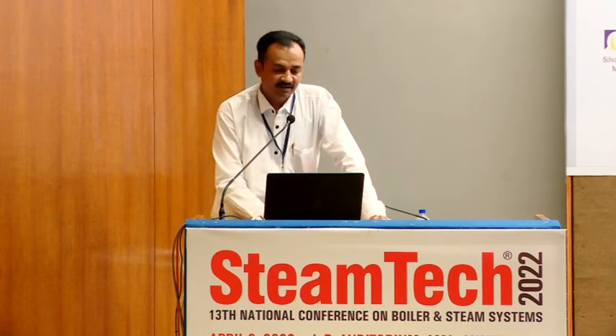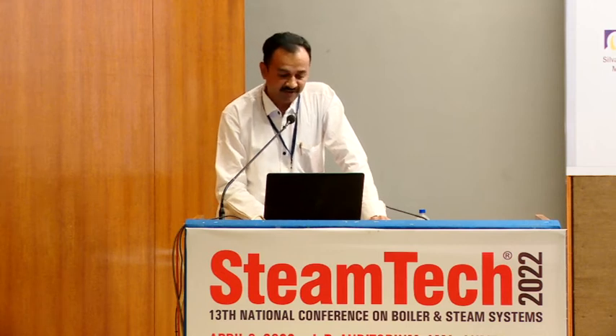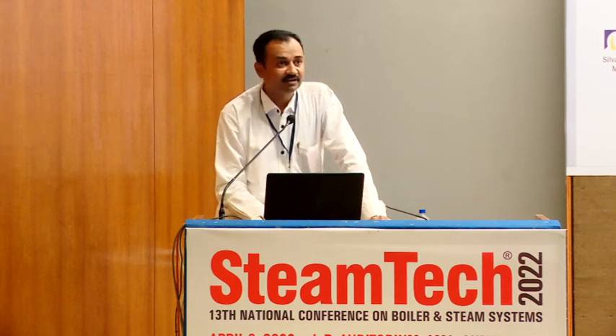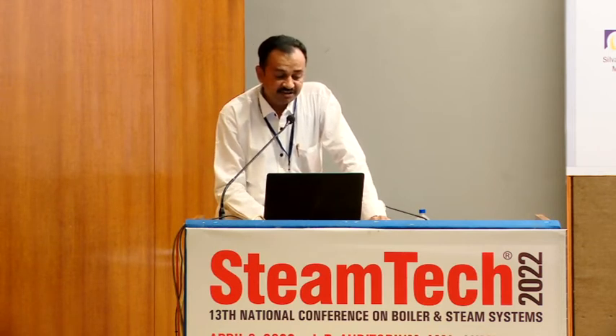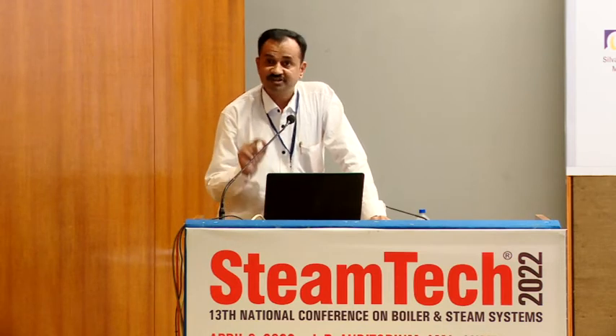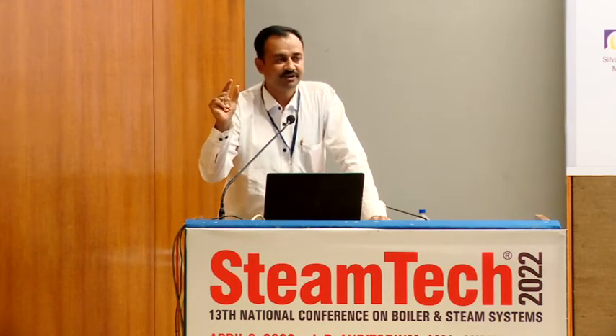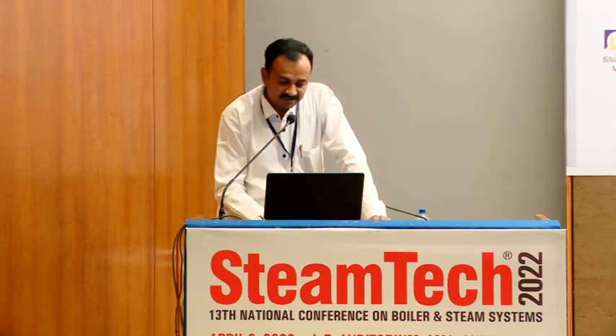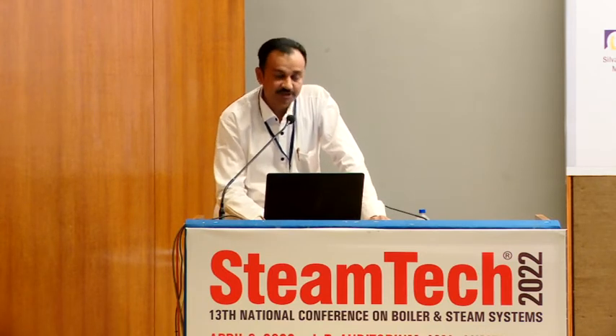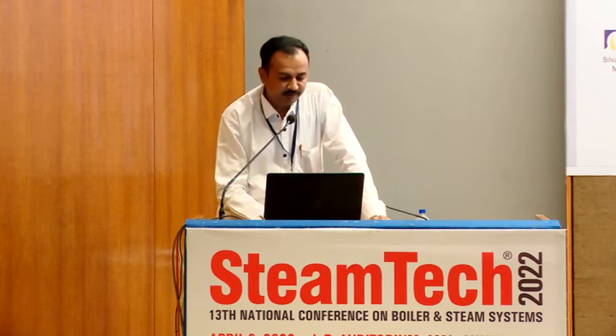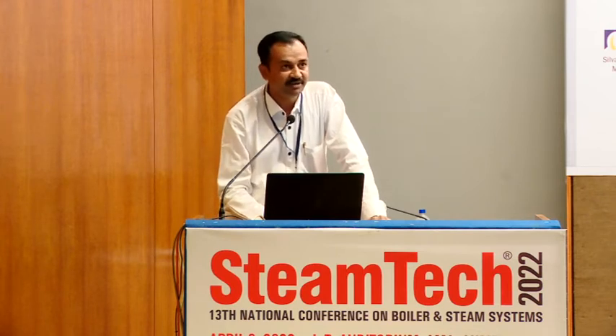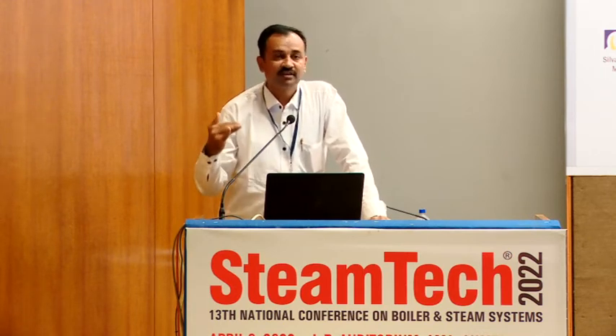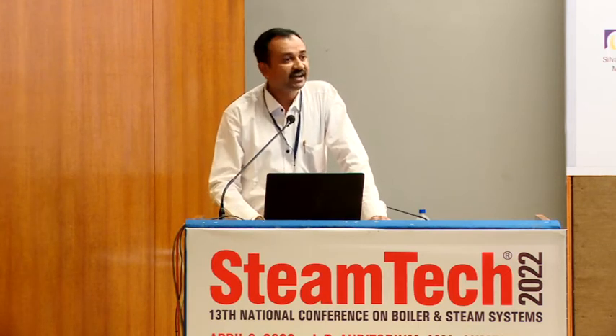On the safety part, again I am taking this as an example, where you can see this live site connected, the mimic of one of the live sites, where you can see the draft pressure in the tune of minus 0.66, just above the null point, just above the 0 mm water column. In spite of that, stack oxygen is in the band of 5 to 6%. And all the pressure and temperature parameters are well within the limit. So this gives the idea that the boiler is operating within the safety limit and the efficiency limit, within whatever the rated condition, and the user can get the benefit.